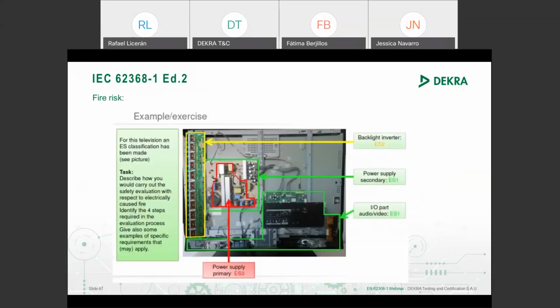Here you have another example, an LCD monitor, and you can see how we can classify the different parts of the circuit. Here, in the center part of the equipment, I have the hazard part. This is the energy 3 part, and the rest of the PCB has reduced energy and another classification. In this example, I am designing an enclosure of the equipment, and I have to review where I can put a grid for cooling the equipment. Of course, never put the grid, the opening, near the ES3 or the PS3 part. Okay, I locate the grid or the opening in the ES1 part.